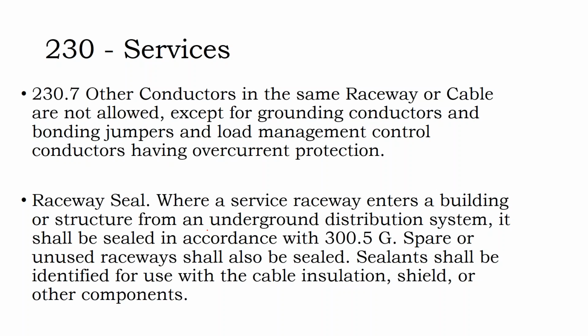Let's see. So other conductors for services are not allowed in the same raceway or cable. And where we see this pick up later on in code is when you get into your solar cables and you say, well, I have AC solar and I have DC solar, you know, you have the DC side plugged into the inverter, the AC side plugged into the inverter. And you might ask yourself, is DC and AC allowed to share the same cable? Or you might have your solar inverters and then a wall display next to it, and you want to run power to a service panel, and you might say, am I able to put regular load circuits in the same raceway as my solar circuit? And there is a section later on in code that says for solar cables, you're not allowed to combine your load circuits with your solar circuits.